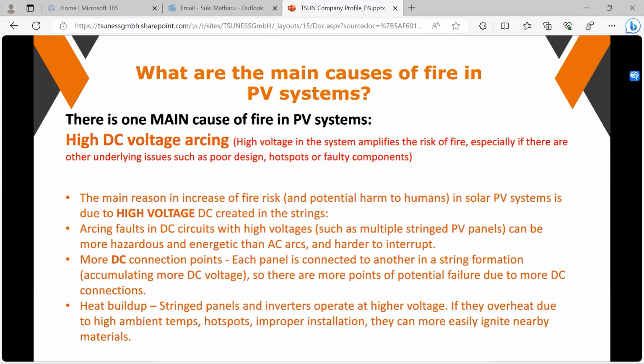The main reason is the high voltage in the strings, and usually the strings are the problem. As you get 5, 10, 15 panels across, the voltage gets higher and higher, and we get to a situation where we need to manage that DC. The majority of the problems in any installation are due to DC. 77% of the research shown on sites says that DC distribution management is a problem, and we need to try and avoid that as much as we can. It's quite easy to do that in domestic systems. We'll go through that a little bit more later on.